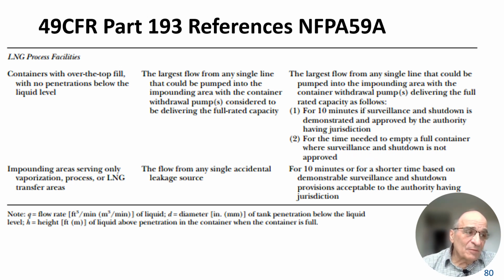So a prudent plant siter would certainly have surveillance and shutdown capability built into their plant, and the design spill would be for a guillotine cut at maximum flow from that tank. So if you have internal tank valves, talk about a guillotine cut, maximum flow from those internal tank pumps, and that maximum flow would be for a period of 10 minutes, and that would be your design spill. For impound areas serving only vaporization or process areas, it is 10 minutes or a shorter time based on demonstrable surveillance or shutdown provisions acceptable to the authority having jurisdiction.